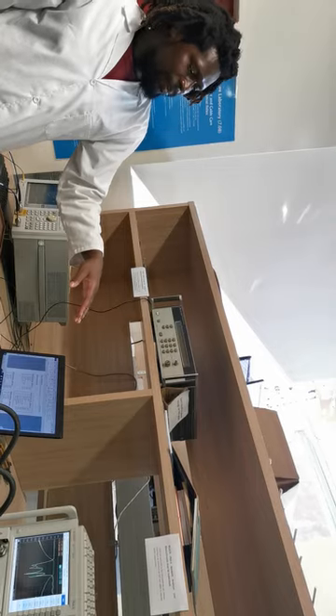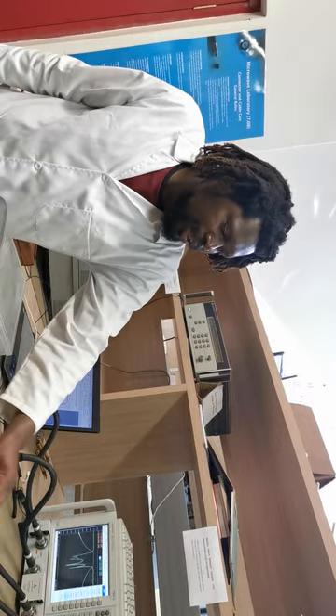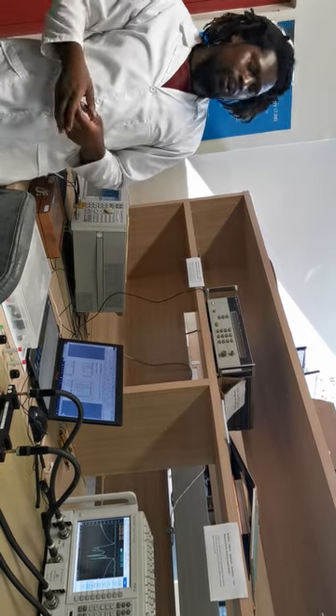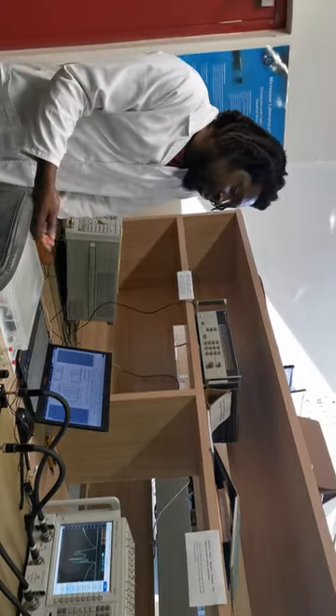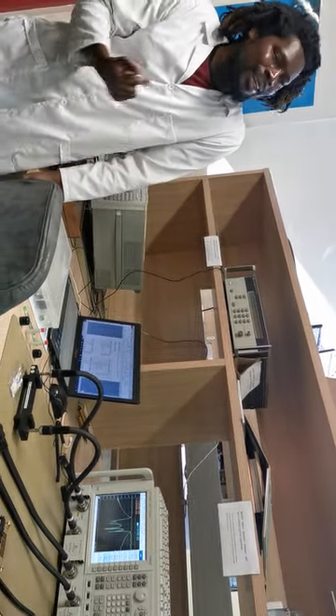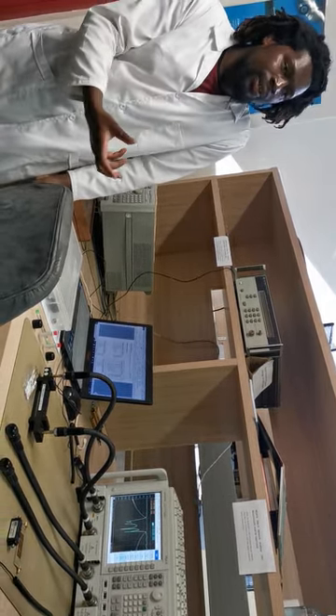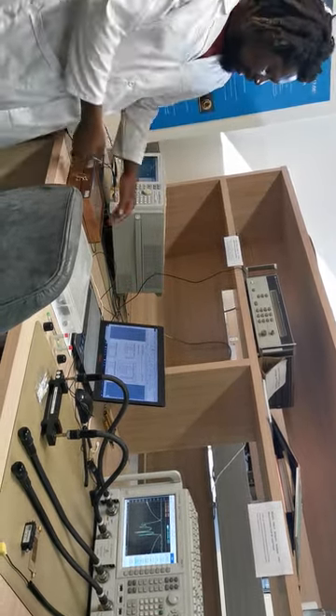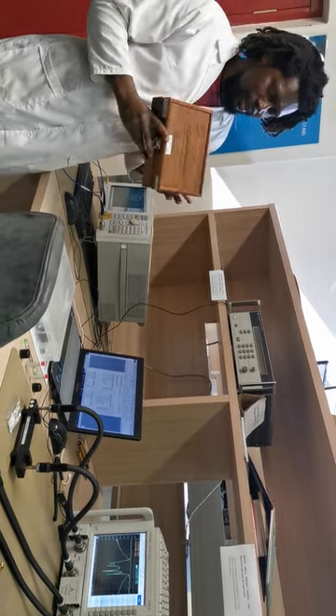For calibration: when the cables are shorted or opened, the reflection coefficient should be a flat line at zero, meaning all signals are being reflected. But when you start it up, it's never really like that. You have to do a calibration before every measurement. You can save your calibration and reload it, but it's good practice to redo the calibration periodically to remove all systematic errors from the system before measuring your actual device.